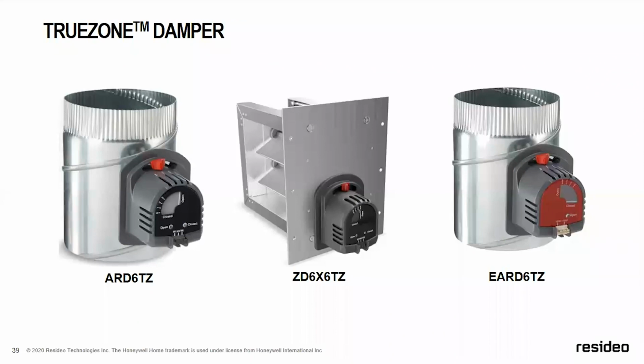As you can see on the ARD and the ZD, the actuators are actually identical. The EARD is an exhaust damper. So the ARD and the ZD are power closed. The EARD is power open. So if you're doing forced air zoning and your damper actuator fails, you want it to fail in the open position. Typically, if you're bringing fresh air in, you want it to fail in the closed position.